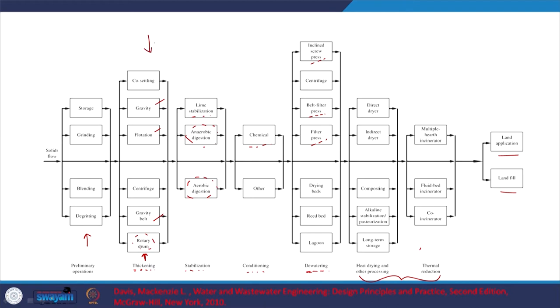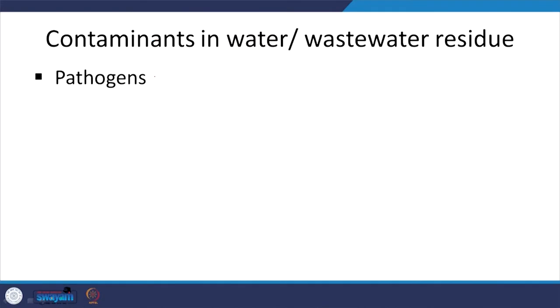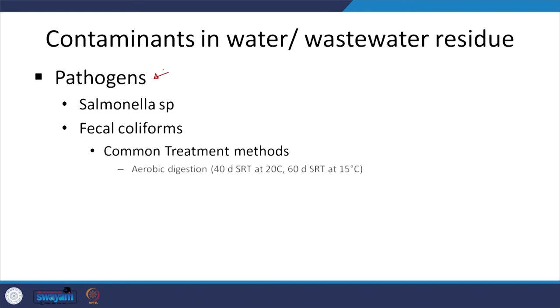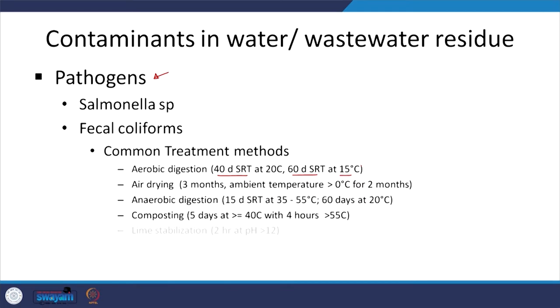The first step is thickening. Before moving on, I want to give an idea of the specific objectives. In the Indian context we may not have them clearly spelled out, but many countries do. We are trying to decrease the concentration of pathogens in the sludge. There are other aspects too — putrescibility or biodegradability that we want to decrease — but major concerns are pathogens. Fecal coliform and salmonella. Methods include aerobic digestion at 40-day solids retention time at a particular temperature, or 60-day SRT, air drying, anaerobic digestion, and composting. We will look at these later.